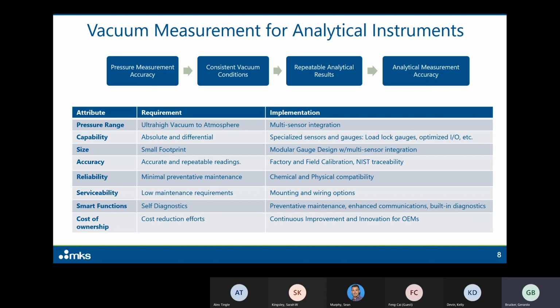Pressure range: we have to be able to go from ultra high vacuum to atmosphere with our product line, which typically means the gauges you end up buying will incorporate multi-sensor integration. We have to be able to do absolute and differential pressure measurements. In fact, you'll typically end up with gauges that are specialized for the type of measurement you need to do. You can buy load lock gauges, for example, that take care of the automation of your load lock.